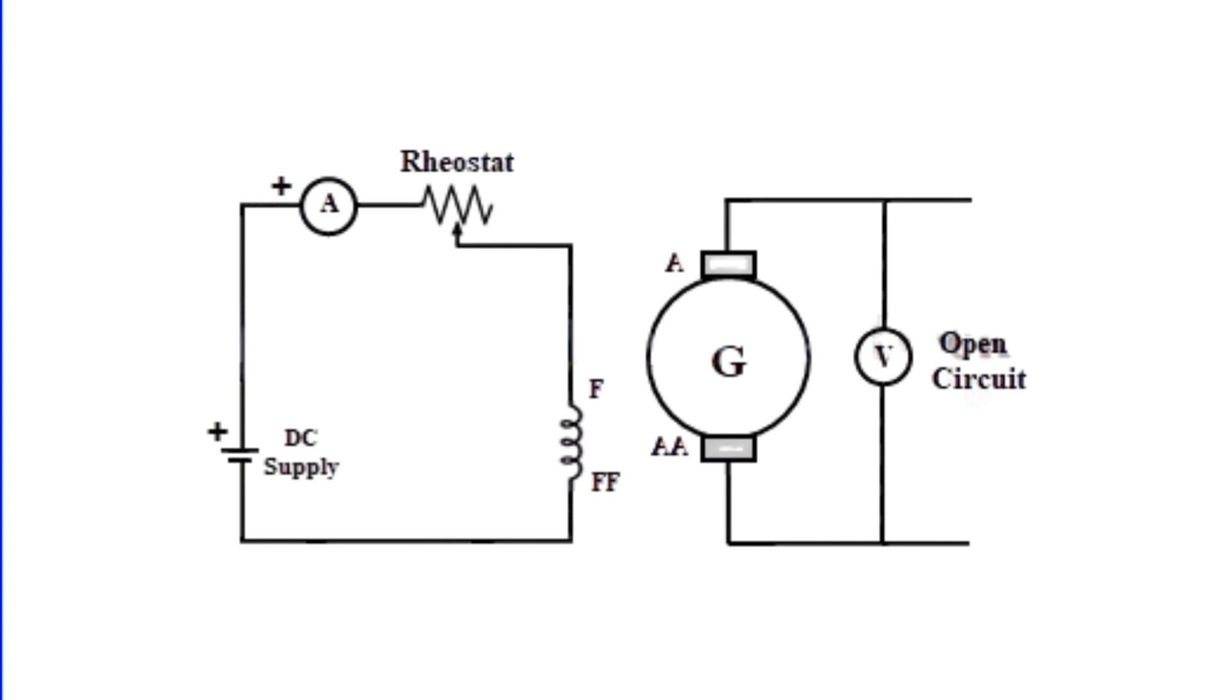The image shows the experimental setup. The field winding is separated from the armature circuit. It's connected in series with an ammeter to measure field current and a rheostat to control resistance. An external DC source is connected to excite the field winding. The armature circuit is open circuited. A voltmeter is connected across the armature terminals to measure generated EMF.